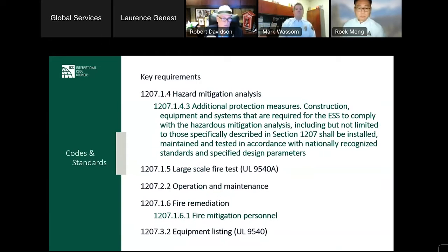So one of the key things to highlight is that in the hazardous mitigation analysis, when they're looking at how everything relates, they may identify additional protection measures above and beyond what's already written into these standards. And those have to be installed appropriately in accordance with proper nationally recognized standards. The other thing I'd like to point out here is, though in the IFC we have a separate 1207, and in NFPA we have NFPA 855, which is extracted in NFPA 1, sometimes we see applications come at the AHJ level, where I do work, where they don't recognize they have to comply with the whole code. In other words, you'll bring something up like, we're going to need fire hydrants and fire flows. Well, that's not in any NFPA 855.